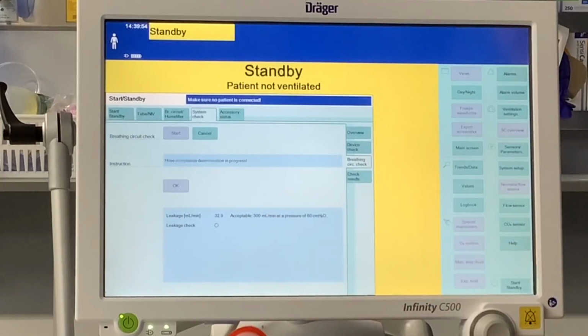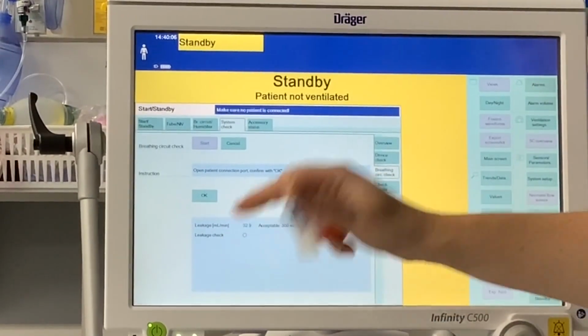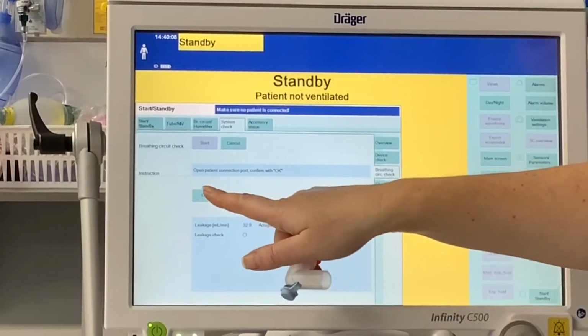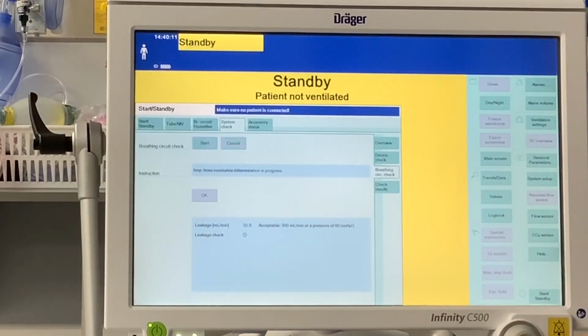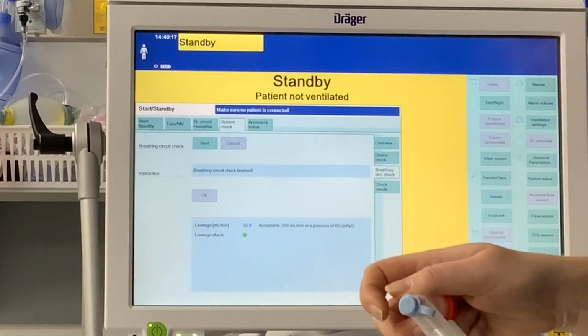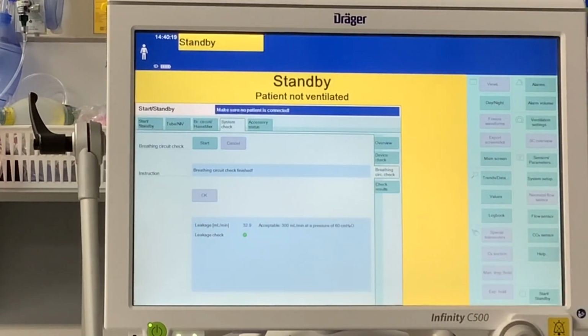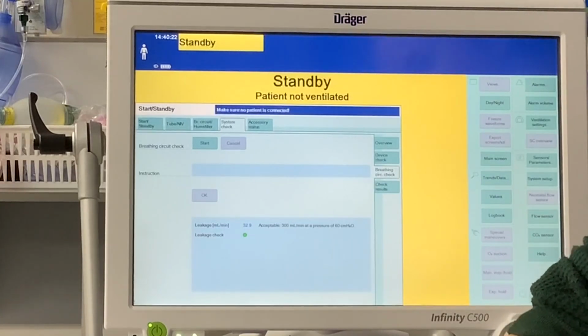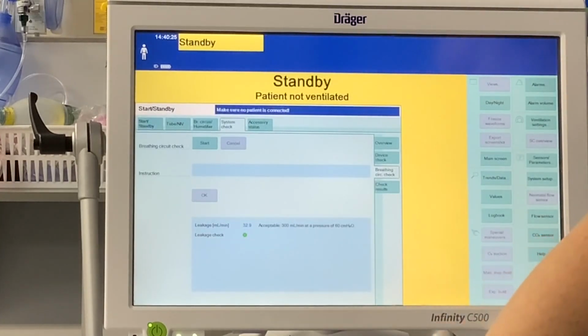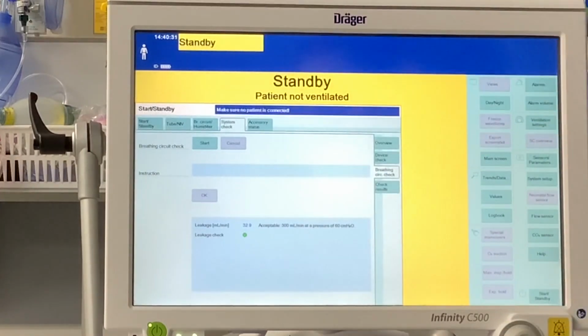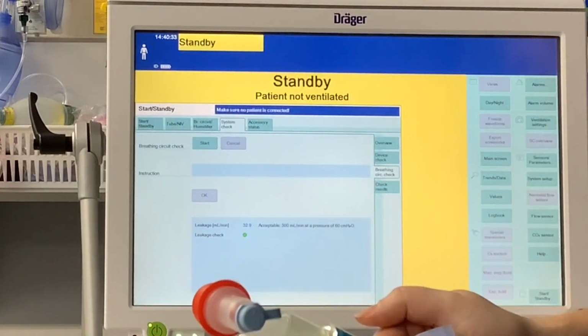Acceptable is 300 milliliters per minute at a pressure of 60. So it's under it. If we did have a little leak in the circuit, this is where you're going to see it. It asks us to open it and then confirm with OK. So the breathing circuit check is finished and leak check is good. So if we had, say, a small leak somewhere in the circuit, I will take this off from here. I'm going to make a small leak in the circuit here.